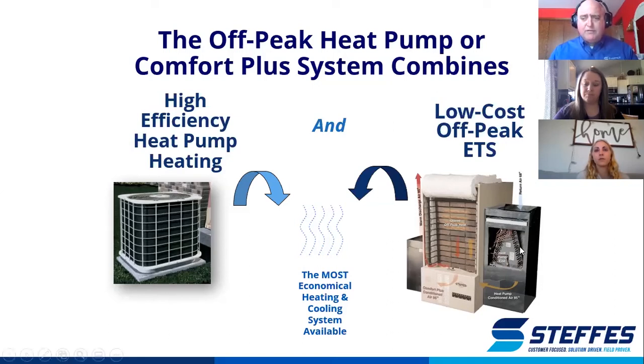When you look at our system, the indoor part of the heat pump is this A coil, and the A coil sits in the return side of the Steffes system. And so what happens is when there's a heat call, the heat pump starts up, we start to bring air through the ductwork, and we let the heat pump do as much work as it can. We allow that heat pump to efficiently add heat into the ductwork.